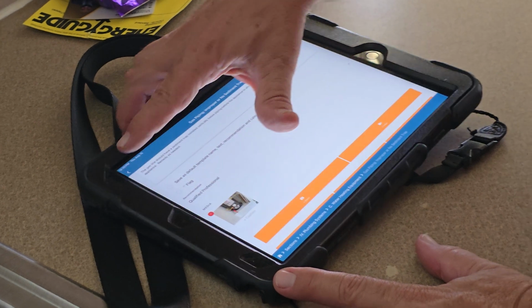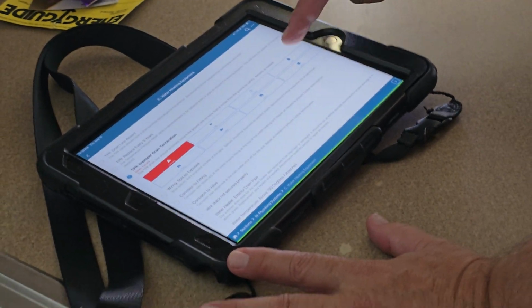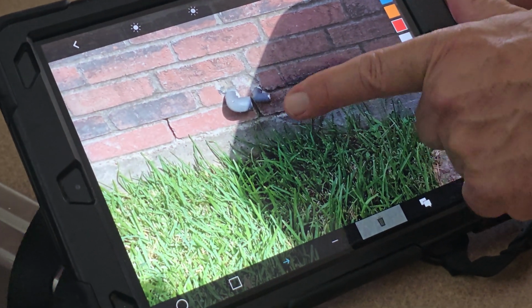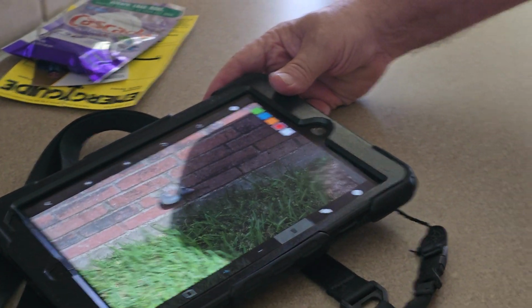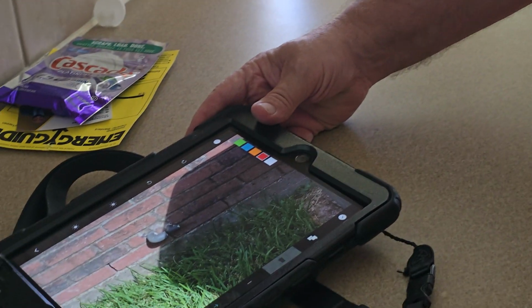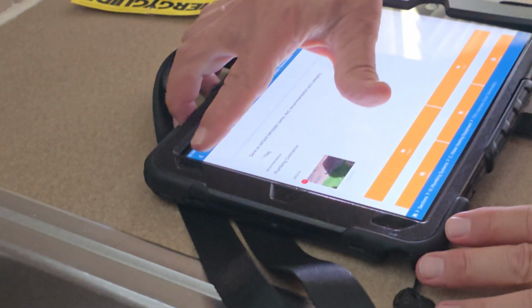And then on the temperature pressure release, it's not facing the ground. It's facing sideways. Now, that's on the left side of the house. It's not in a high traffic area, but it should point down because if it ever does release, it's 200-degree water that's coming out at 150 psi. It should point straight down so it doesn't spray anybody.